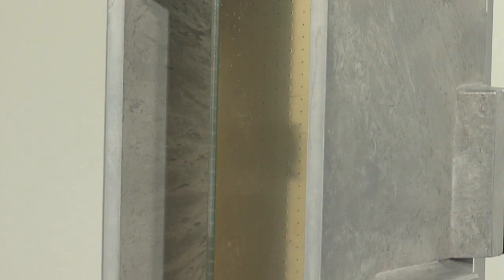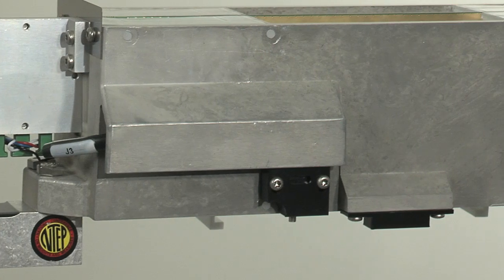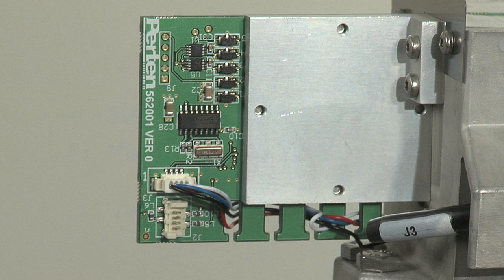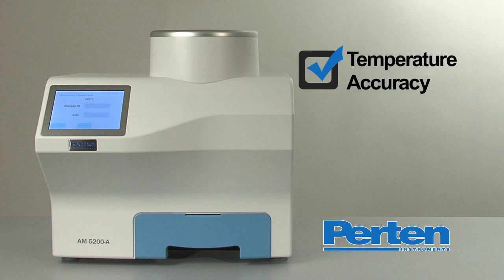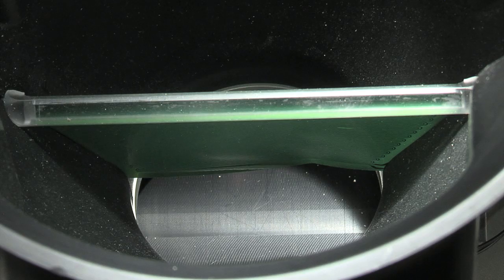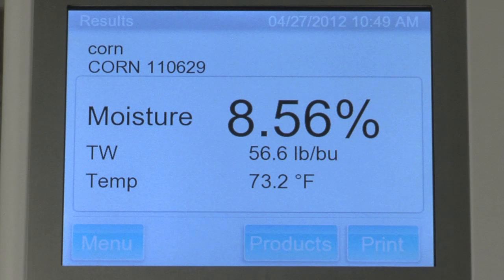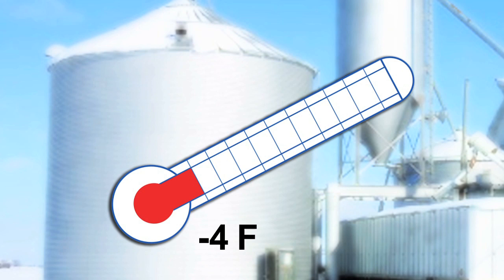The heart of the Perten AM5200A is a single-piece cast aluminum cell, ensuring accurate, precise manufacturing, resulting in accurate, reproducible measurements of volume and density across all instruments. The PC board is integrated into the cell, removing problems caused by cables and connectors. Grain temperature is obtained quickly and accurately through direct contact with hundreds of kernels. The large surface area of nearly seven square inches, coupled with the low mass of the detector, ensures grain temperature is measured fast and accurately, even for frozen grains at minus 4 Fahrenheit.